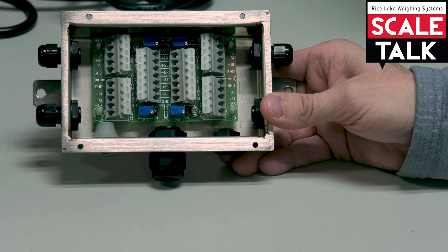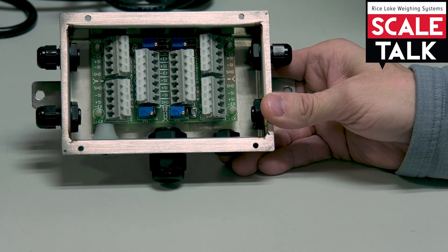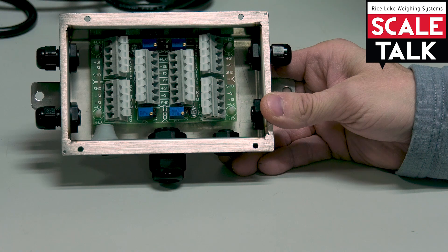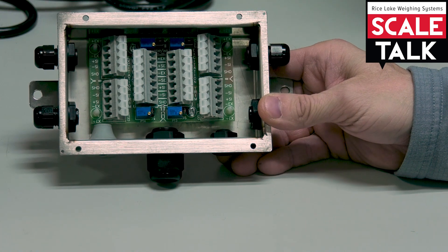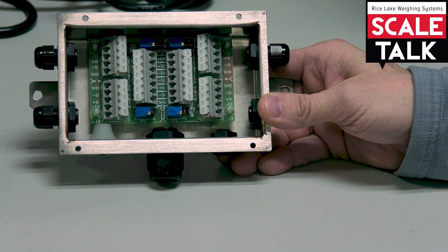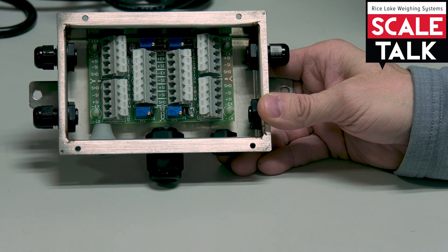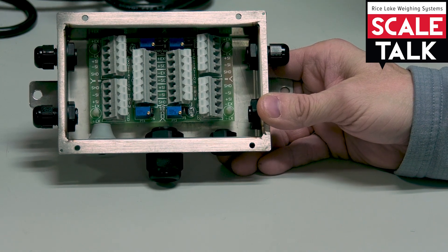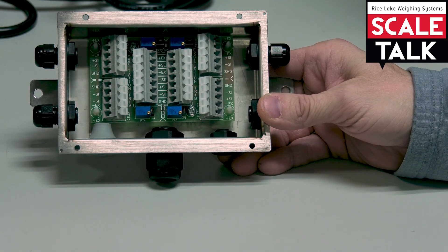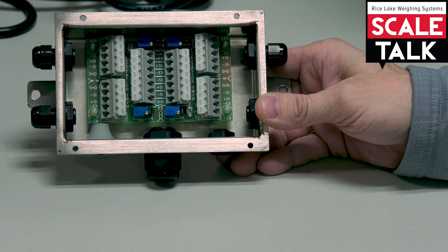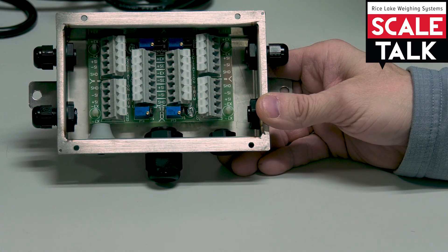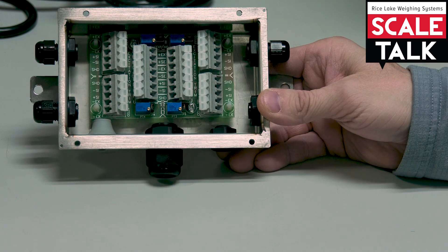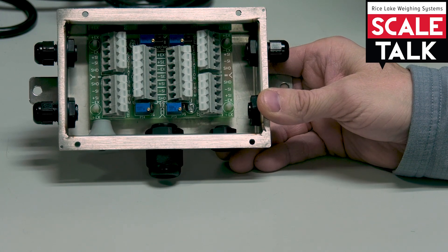So again, our J-Box allows us to bring multiple load cells together to form a single scale, gives us the ability to trim off differences between cell to cell and achieve the same signal weight ratio so that I can read the same weight no matter where I am, provides environmental protection for all of my connections, and allows me a nice convenient place to take all of the measurements I need.